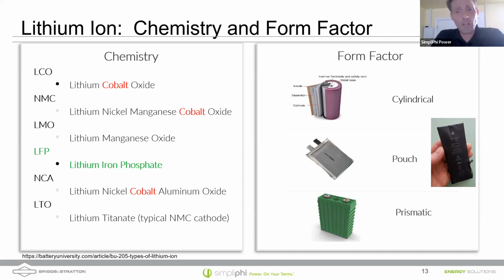So let's talk about the other kinds of cells. So we want to avoid pouch cells for installations that we're hoping to last for long times. And the other two options are prismatic cells, which have many good qualities. They typically come in very large sizes. These large sizes allow for lower costs compared to cylindrical cells, but they're almost always made out of plastic casing, and that plastic casing, especially with the geometries, ends up expanding and contracting more with time, with charge and discharge cycles.